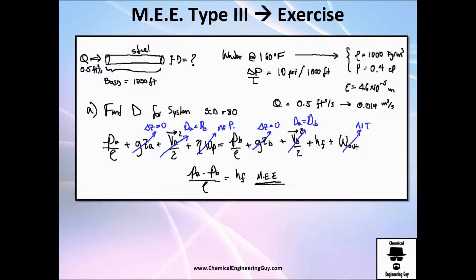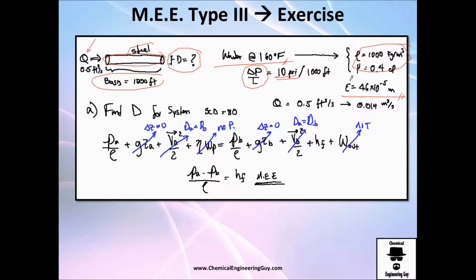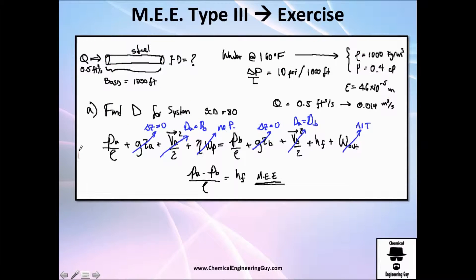Let's do this exercise. We have a steel pipe, a volumetric flow rate, a length of 1000 feet, and a known water temperature with given properties. The pressure loss is 10 psi per thousand feet. Since it's steel, we can find the roughness, and we need to find the diameter given it's a Schedule 80 pipe. Writing the mechanical energy equation: we cannot cancel pressure because there is a pressure loss. We can cancel height since both points are at the same level, and we can cancel velocities because the diameter is the same throughout.